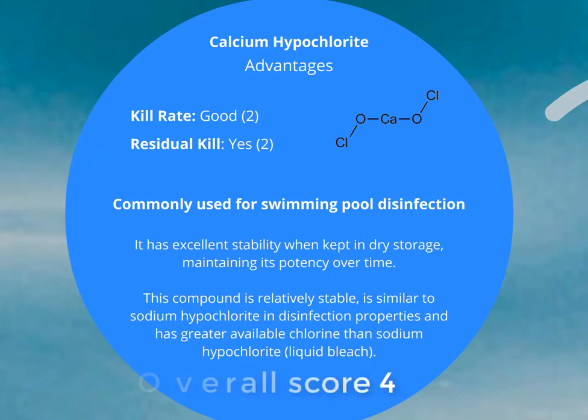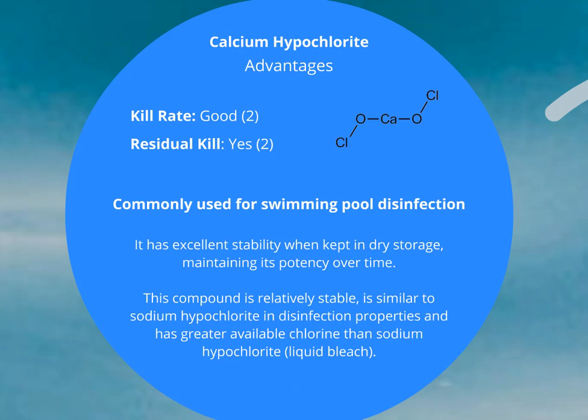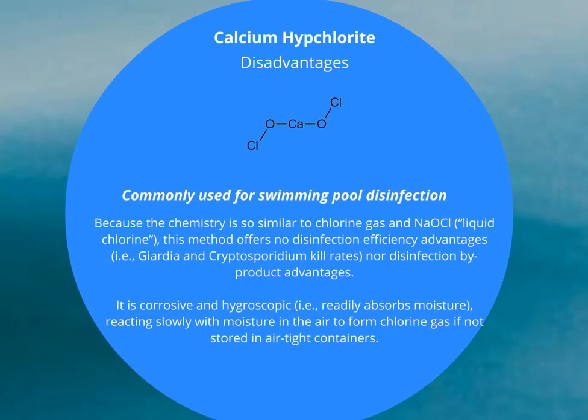Calcium hypochlorite has a good kill rate and residual kill, and is commonly used in swimming pool disinfection. It has excellent stability when kept in dry storage and maintains its potency over time. It's relatively stable, similar to sodium hypochlorite in disinfection properties, and has a greater available chlorine than sodium hypochlorite or liquid bleach. However, it is corrosive and reacts slowly with moisture in the air to form chlorine gas if not stored in airtight containers.